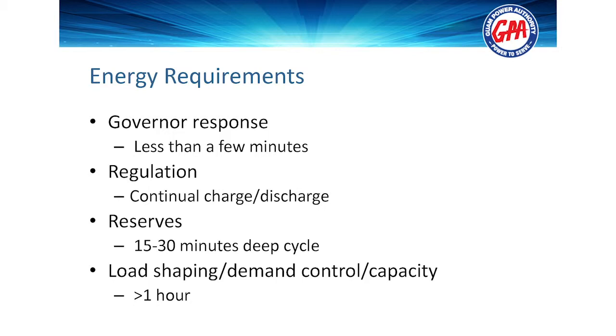So what are we trying to accomplish with energy storage? This is what you're trying to replace, the governor response. In the power system today, GPA is all thermal generation. What a governor does is look at the power system frequency at 60 hertz. If the system frequency is not 60 hertz, the governor is the accelerator or the decelerator that changes the generator's fuel supply to get to 60 hertz. As you move towards a new generation regime and you're taking away your regulation and your reserve margin, something needs to take the place of that governor, right? Because you reduce the number of units that you're operating. So something needs to take the place of that governor response, and that's stored energy.